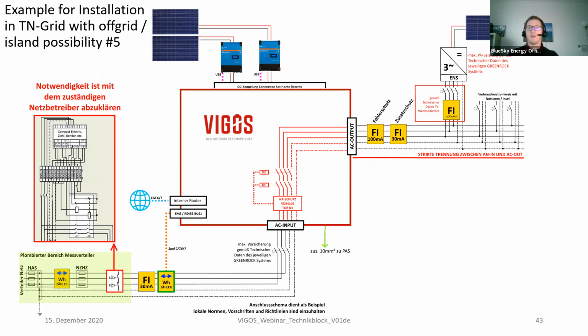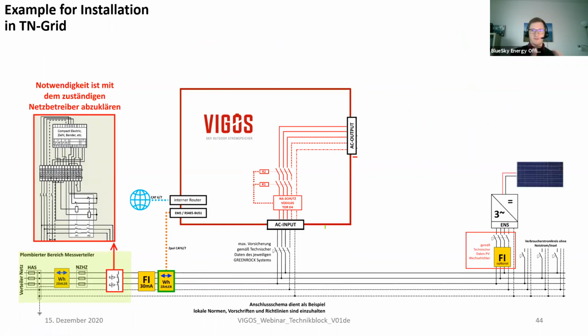It's possible, but please always be aware of the maximum amps which you are driving through the AC out to AC in, or AC in to AC out, transfer current. This is listed inside the datasheet. The different system sizes have different transfer currents available. So please take a look inside there to not exceed the maximum current on the outside. But please don't get confused. This is the standard installation of a system. The function will always stay the same.